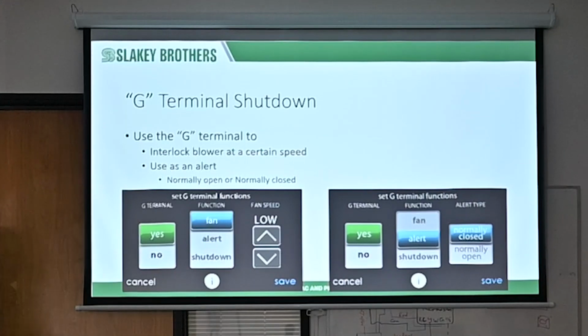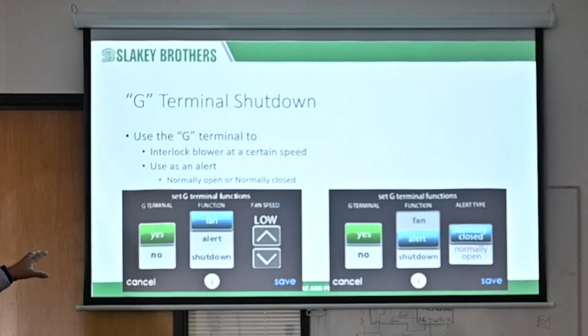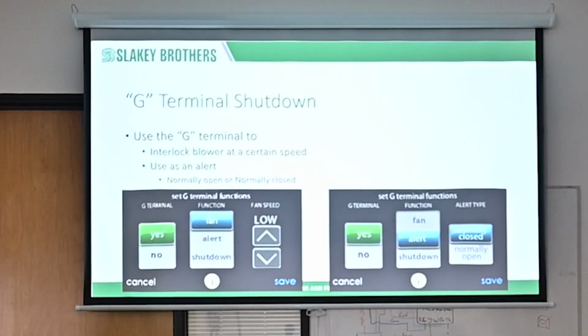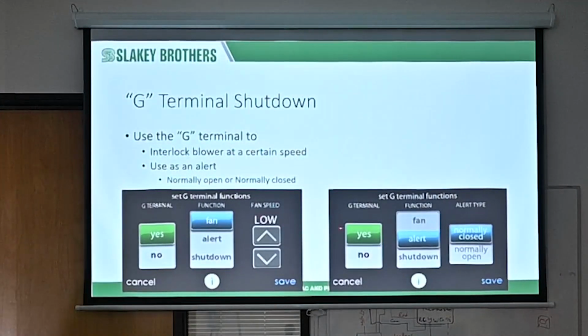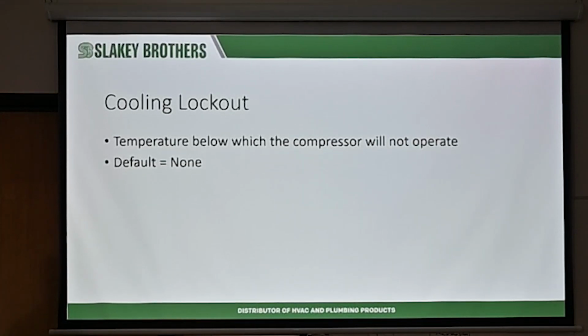Or an ERV. An ERV needs ventilation, needs air to be flowing, needs the fan to be flowing. If your ERV control needs the fan to come on, it closes R to G, and that signals, in this scenario, to just turn the fan on. But with a condensate pump, now we want the unit to shut down. Or let's say you put this in an elderly home and you need global shutdown. You want everything to shut down, no airflow at all, for safety, for a smoke detector, for a fire alarm, whatever it may be. Now you can use a shutdown feature or alert feature. And you can get that sucker to shut down when they really shouldn't be turning that on. You can do the opposite. Besides not having low ambient cooling enabled, you can just tell it that if it gets to a certain temperature outside, never allow the outdoor unit to come on.